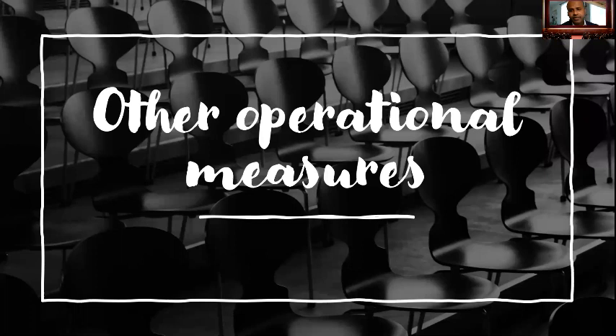Buildings should definitely consider extending the operating times of HVACs before and after the regular period so that the system keeps running and there's more outside air. Many building HVAC systems employ energy-saving settings such as demand-controlled ventilation controlled by a timer or carbon dioxide detectors. Those strategies should be avoided as they limit the amount of outside air intake needed to reduce the contamination.